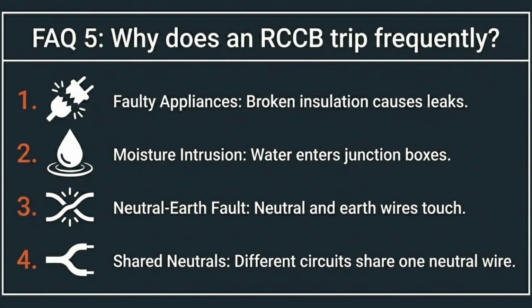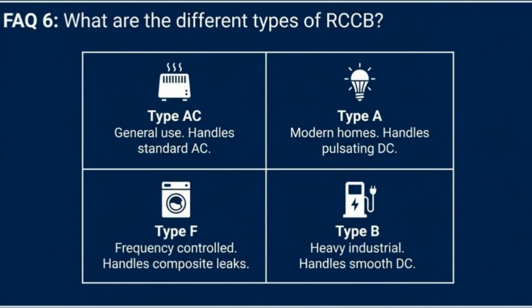FAQ 5. Why does an RCCB trip frequently? Common causes include faulty appliances with broken insulation, moisture intrusion in junction boxes, neutral earth faults, and shared neutrals between different circuits.